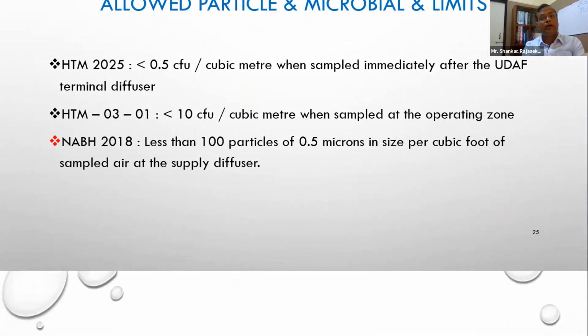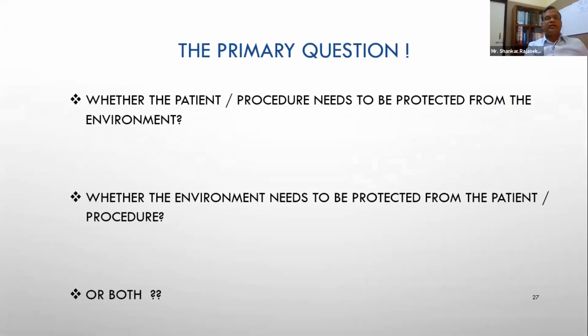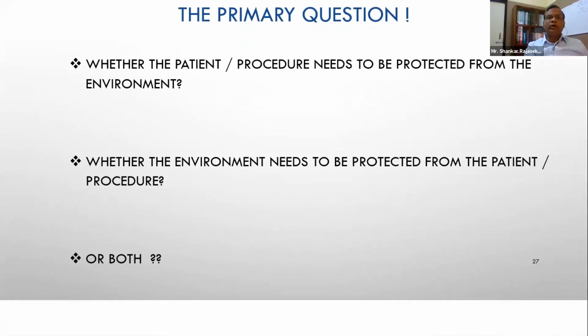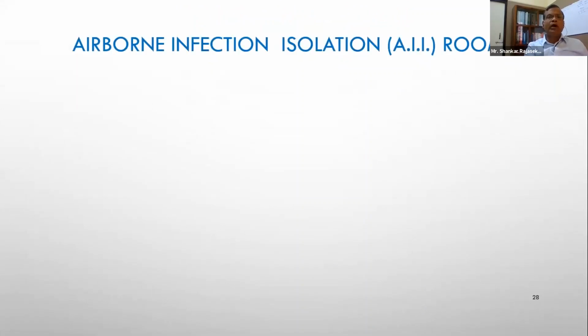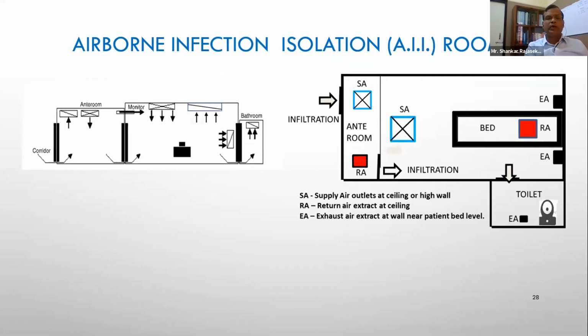So we'll quickly come to isolation rooms. They're talking about whether the patient is to be protected from the environment or the environment needs to be protected from the patient. So we are now talking about airborne infection isolation rooms. After COVID, this has become very popular. It has to be a negative pressure room, and the return air will have to be sucked from close to the patient, and the supply air will have to be provided from the entry part of the room. So there will be a sweeping action towards the patient so that the patient's aerosols are not transported outside.